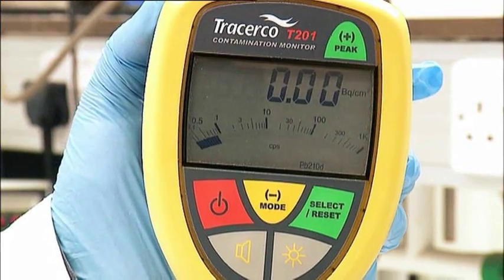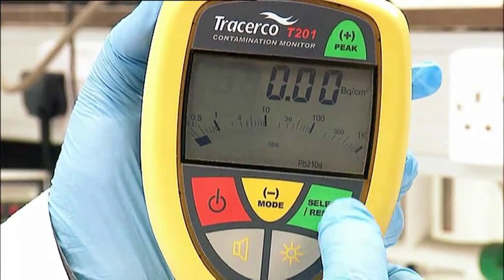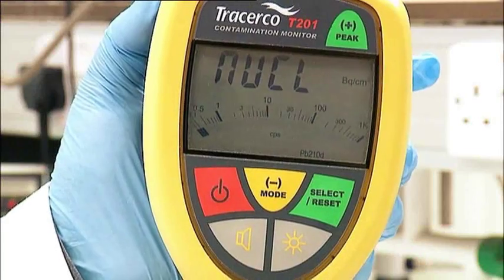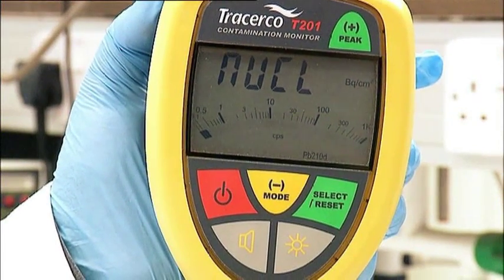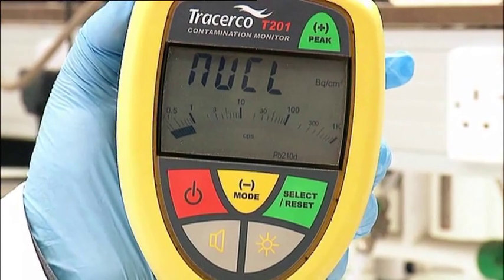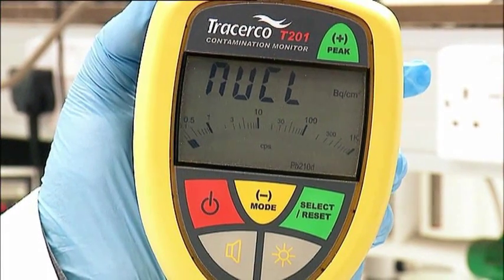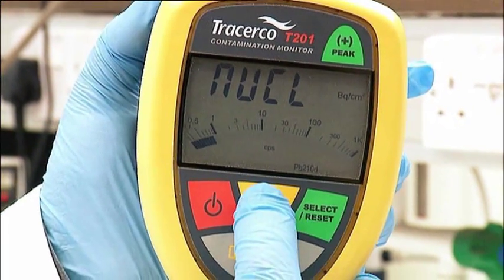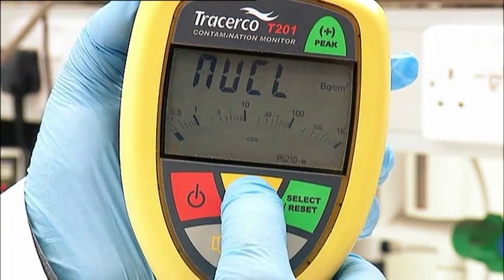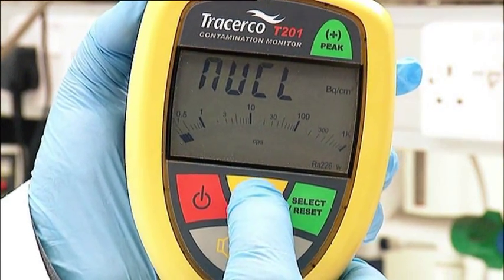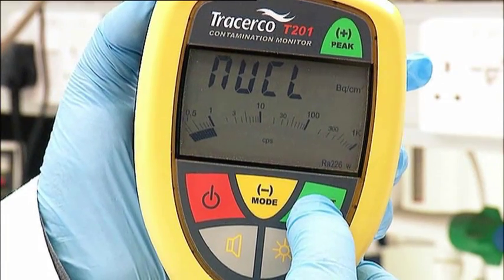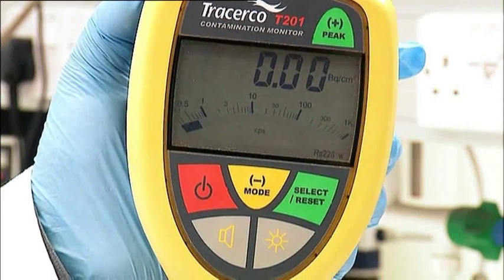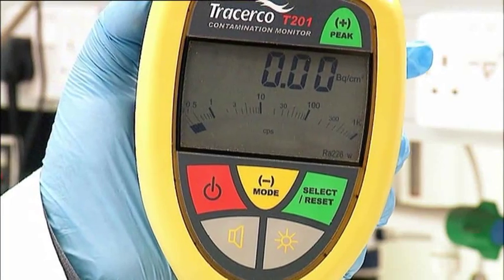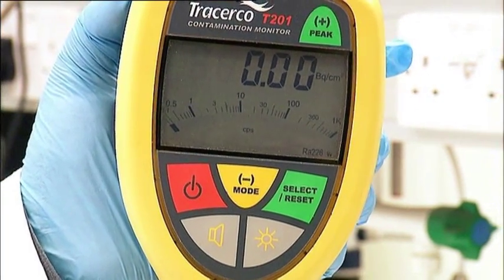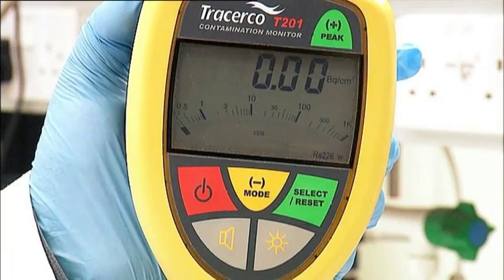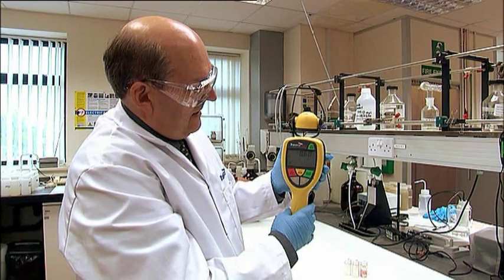In order to confirm the selection of becquerels per centimetre squared function, repress the Select Reset button. The message NuCl will appear on the screen. The various radionuclide options can be scrolled through by repeat pressing of the Mode button. When the required radionuclide is displayed, select it by pressing the Select Reset button. This operation will start the count integration, which will display the real-time value in becquerels per centimetre squared of the chosen radionuclide when measuring surface contamination.